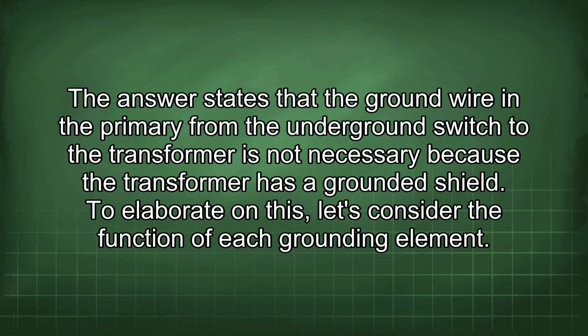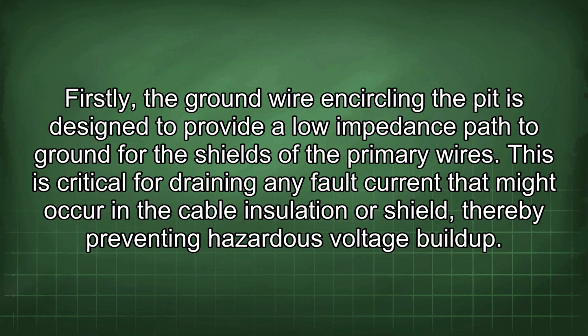The answer states that the ground wire in the primary from the underground switch to the transformer is not necessary because the transformer has a grounded shield. To elaborate on this, let's consider the function of each grounding element. Firstly, the ground wire encircling the pit is designed to provide a low impedance path to ground for the shields of the primary wires. This is critical for draining any fault current that might occur in the cable insulation or shield, thereby preventing hazardous voltage buildup.